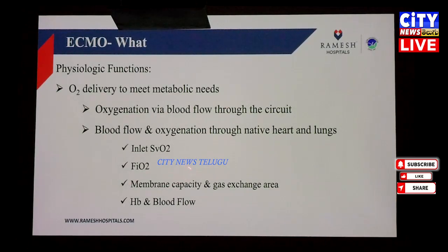The type of membrane oxygenator and the amount of gas exchange area, because different oxygenators have different gas exchange areas. The larger the gas exchange area, the more the oxygenation. What is the baseline hemoglobin of the patient and how much blood flow corresponds to cardiac output. So what is the blood flow that you are giving? The higher the blood flow, the more the oxygenation. So these are the factors which will affect your oxygen supply in the ECMO circuit.